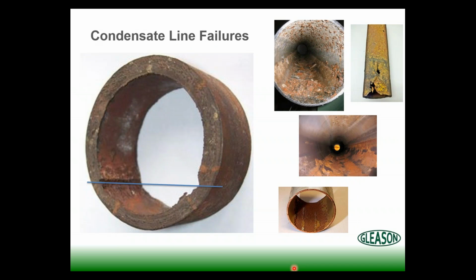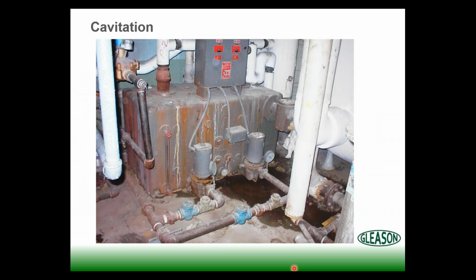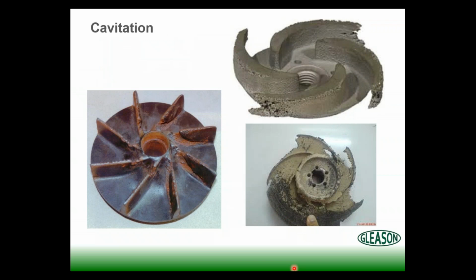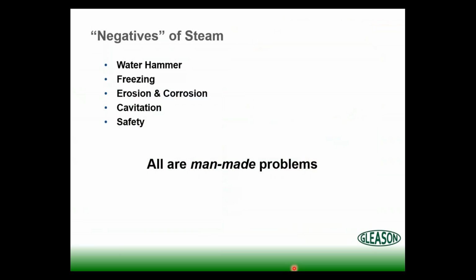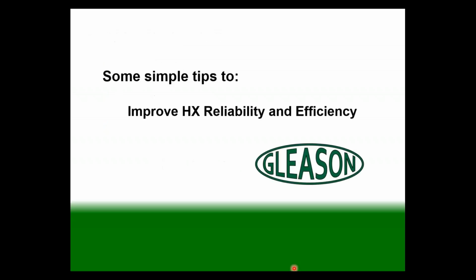Condensate lines, carbonic acid corrosion can be an issue. We'll talk about that here in a minute. Cavitation in any of your condensate return pumps can do damage to your impellers, your casings. It can mess up your mechanical seals. And all these perceived negatives of steam, these are all man-made problems. Steam is perfect. So all these problems are man-made problems. We bring it on ourselves. So let's get into the tips.